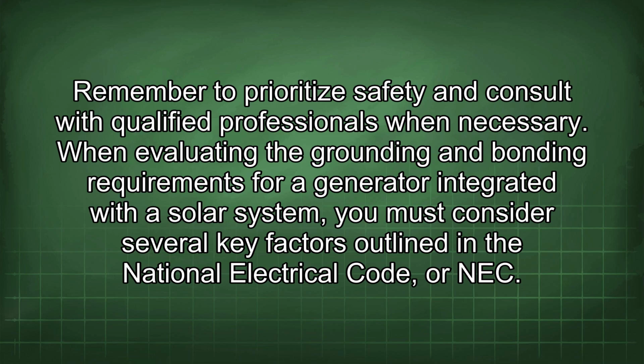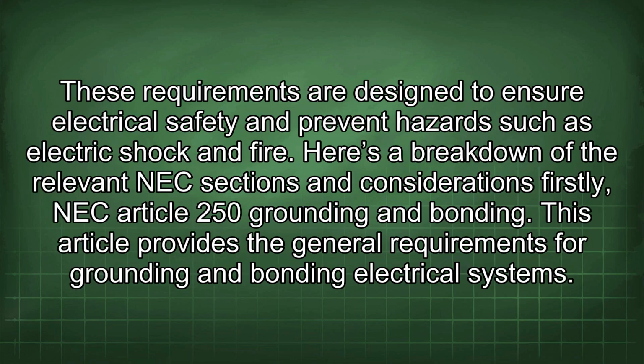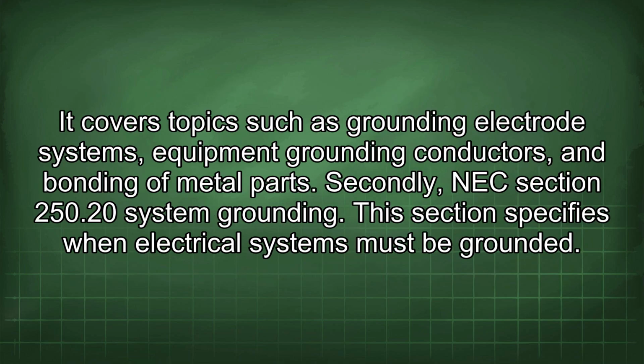When evaluating the grounding and bonding requirements for a generator integrated with a solar system, you must consider several key factors outlined in the National Electrical Code, or NEC. These requirements are designed to ensure electrical safety and prevent hazards such as electric shock and fire. Here is a breakdown of the relevant NEC sections and considerations. Firstly, NEC Article 250 Grounding and Bonding. This article provides the general requirements for grounding and bonding electrical systems. It covers topics such as grounding electrode systems, equipment grounding conductors, and bonding of metal parts.